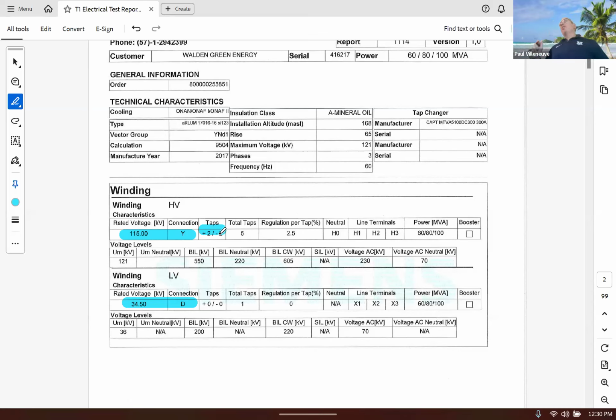Another thing, because some people were asking about it, you'll notice the bushing identifiers. If you take a look at the bushings, you'll see the high voltage bushings are denoted with H's, and the low voltage bushings are denoted with X's, okay? So you know it's a 115 to 34.5 kV, 60 MVA transformer. Y on the 115 side, delta on the low voltage side, and we'll talk a lot more about that when we look at what's called zero sequence filtering. With taps on the primary side, you normally only have taps on one side.